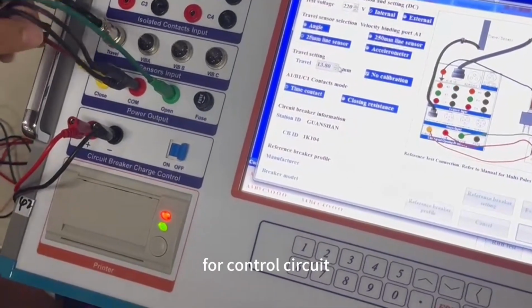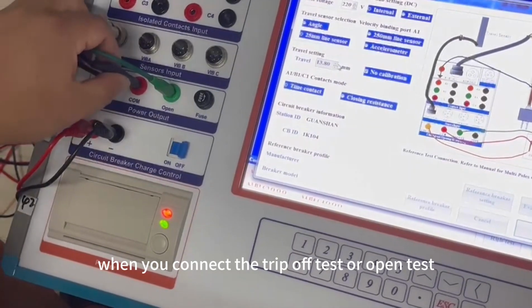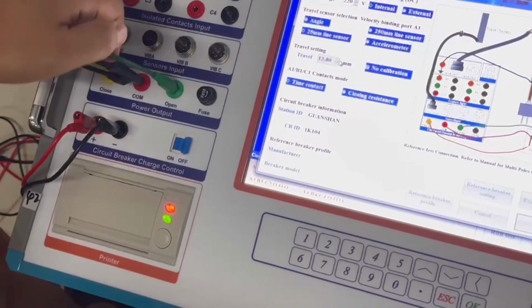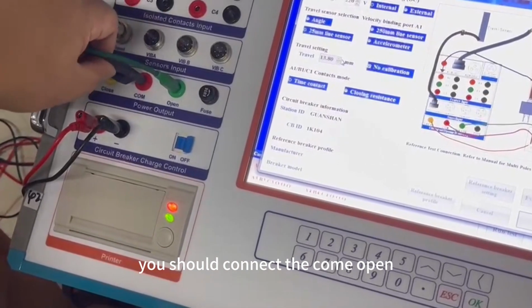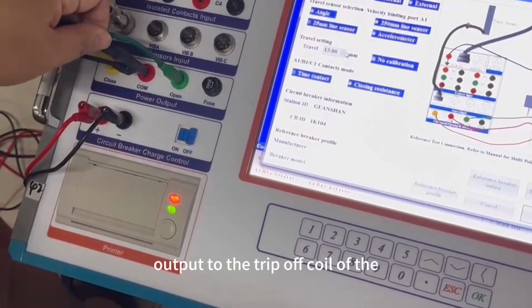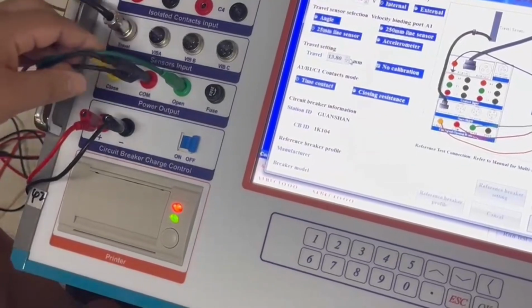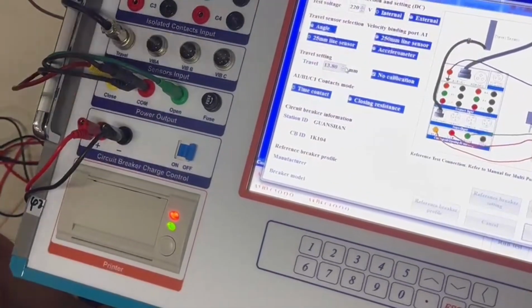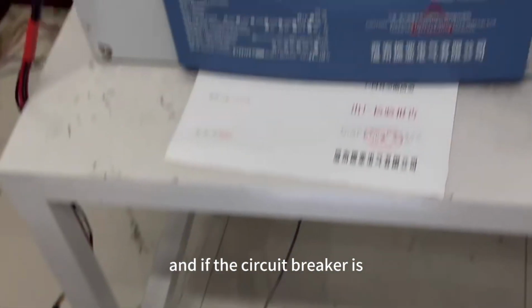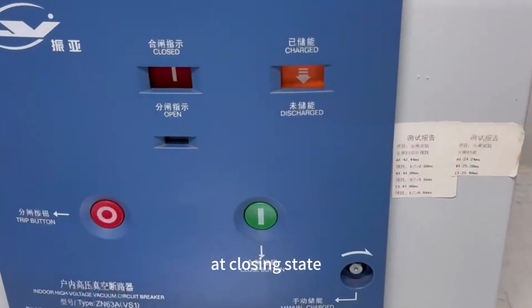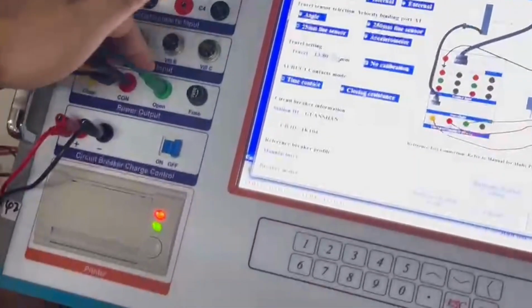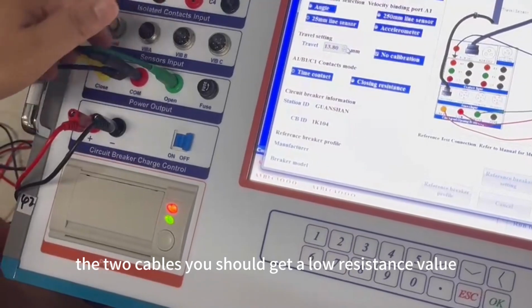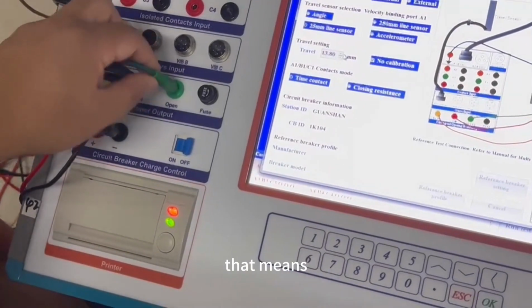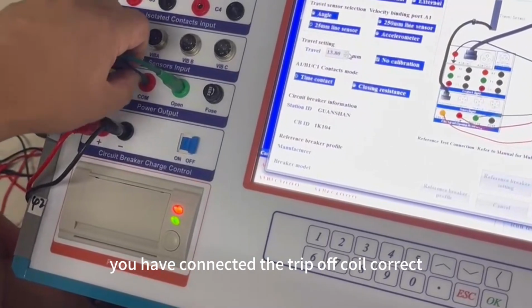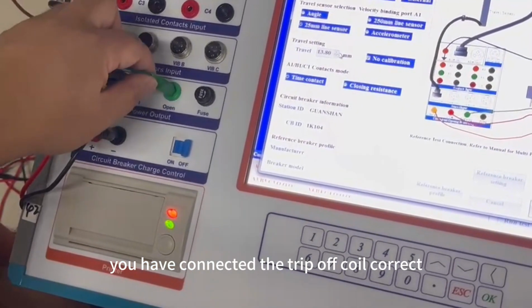For the control circuit, when you connect the trip off tester or opening tester, you should connect the COM open output to the trip off coil of the circuit breaker. And if the circuit breaker is in the closing state, normally when you test the continuity between the two cables, you should get a low resistance value. That means you have connected the trip off coil correctly.